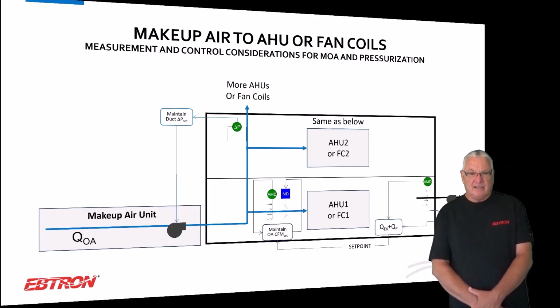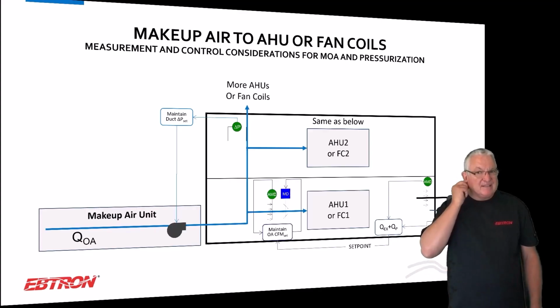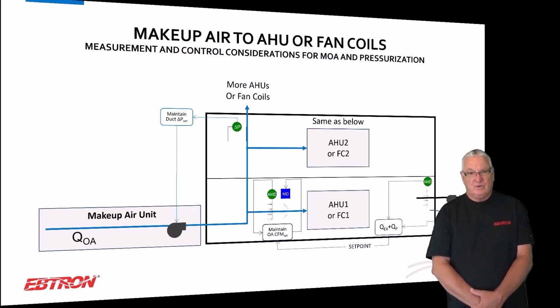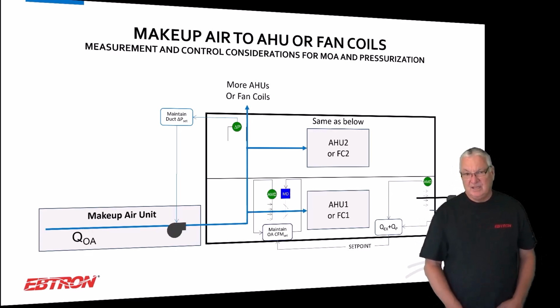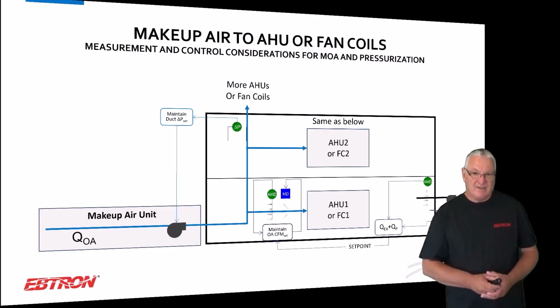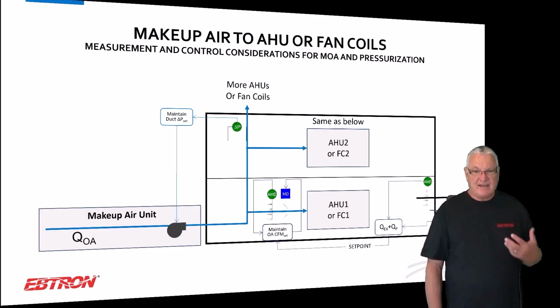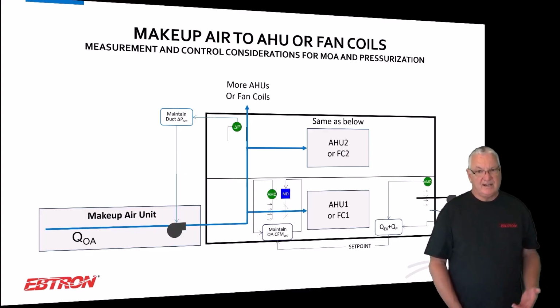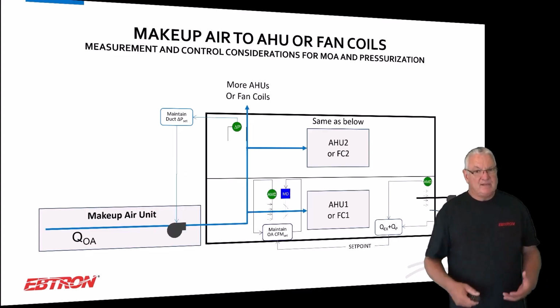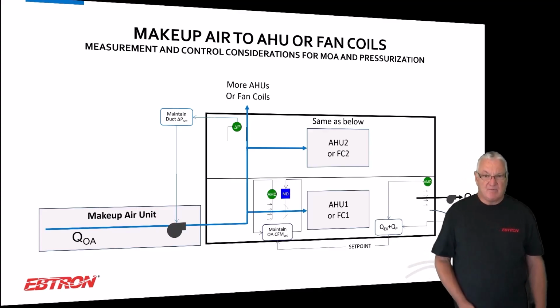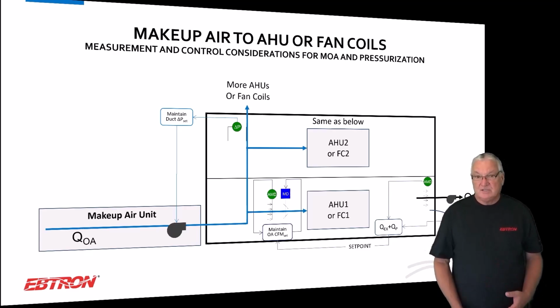Fan coils or multiple air handling units: the big thing I want to say here is you've got to get measurement on the outdoor air. I'm trying to take one slide to do two things. I'm looking at air handlers on multiple floors or multiple air handlers, and I'm also saying it could have been fan coils, or VRF and fan coils. The bottom line is I want to see you get good measurement on that outside air. Those ducts are relatively small, even on the air handlers. We make equipment that's ideal and cost effective for that application. And if there's exhaust, you want to measure it. If it's toilet exhaust, that's another story. Toilet exhaust you may not want to measure. You want to just go on fan status.